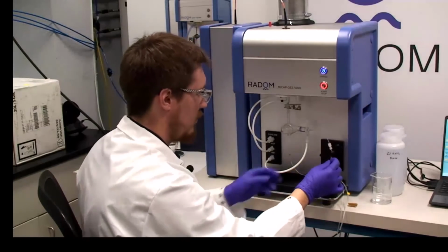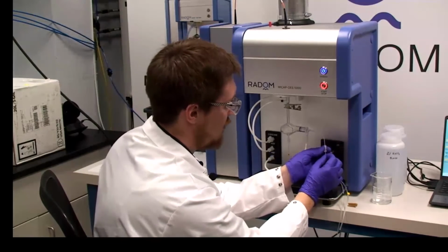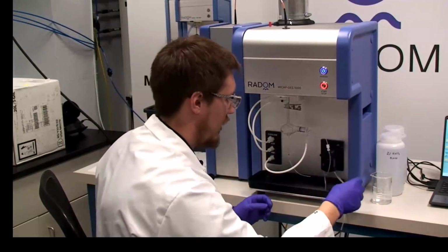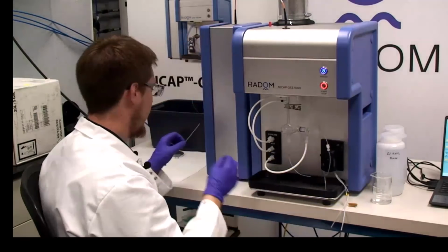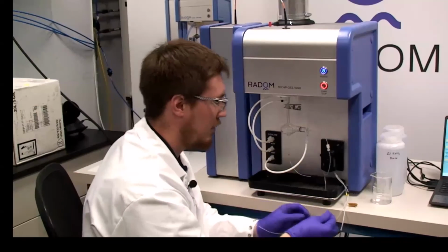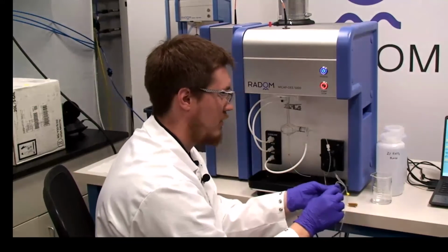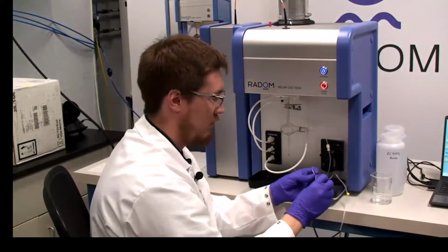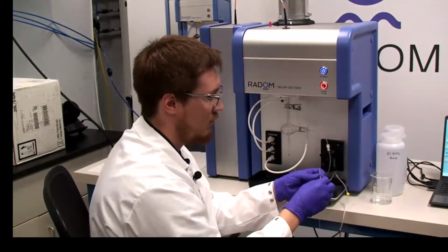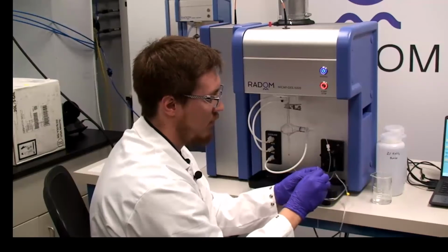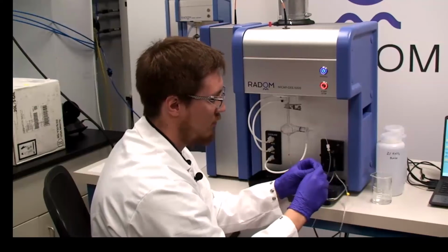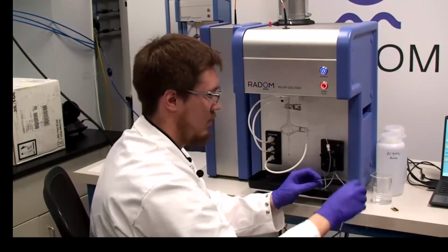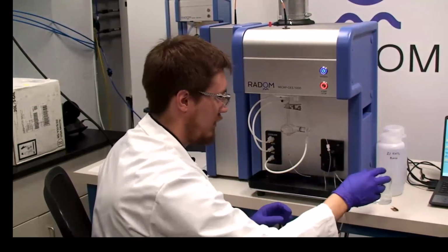Now this sample line will connect to the nebulizer like so, and the other end of the sample line, I'm going to be using this capillary tubing currently as a sipper for our rinse solution. For ease, you can use a small piece of sandpaper to grip the tube so that will prevent any bending, and that'll just use a little bit of force. And so we have that in our rinse.